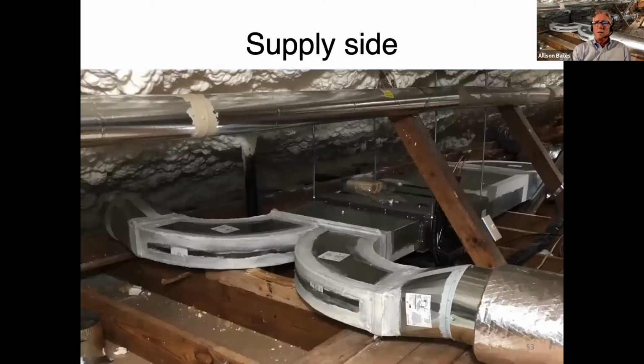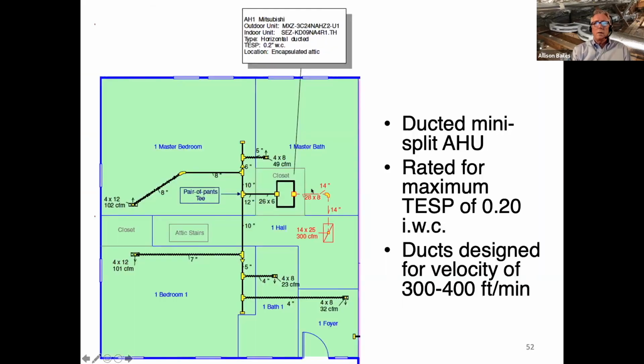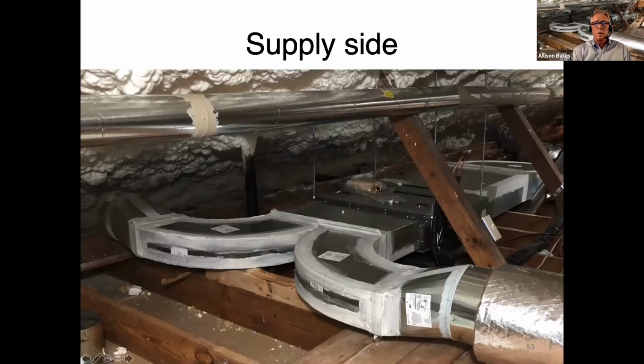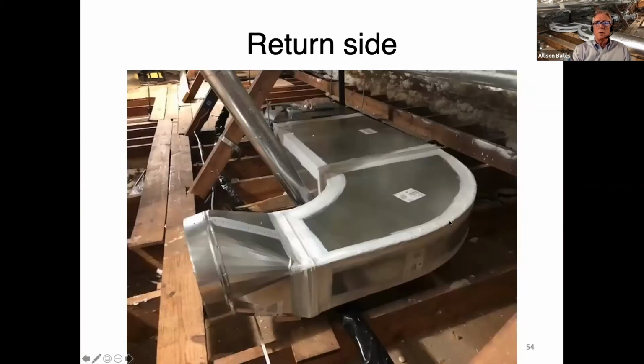here's what that looks like. So in this diagram, this part right here is what that next picture is. So here's the air handler, the plenum, and one part comes out, and this was during installation, so it's not finished yet. This one's not attached to anything over there, and it's not insulated at this point. But the nice radius throat on both of them gives us a good even split of the air there, and low static pressure. This was on the return side.